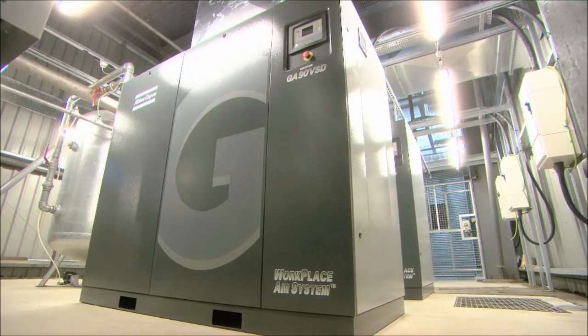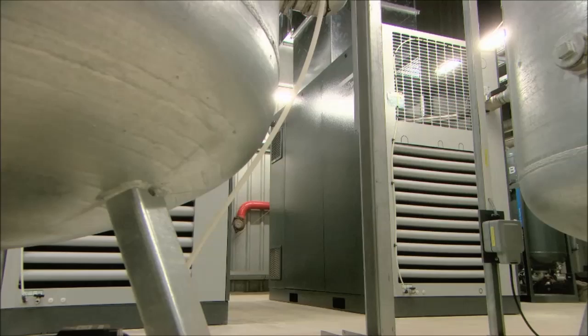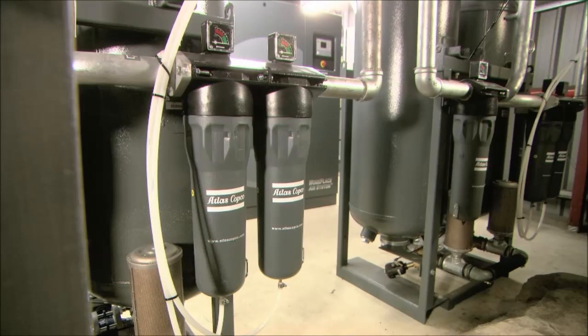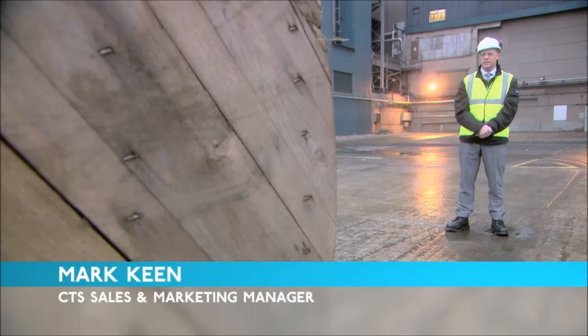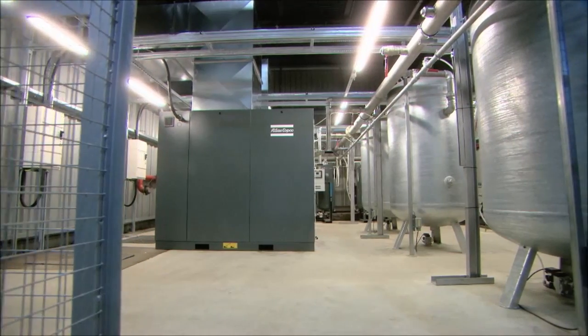The equipment installed comprises two Atlas Copco GA-90 compressors — one a conventional fixed speed and one a variable speed drive for energy savings — three vertical air receivers, Atlas Copco pre-filtration, three Atlas Copco desiccant dryers, and DDP particulate outlet filtration into the customer's ring main. To back this up, we also have an Atlas Copco condensate management system, so we offer a total system solution.